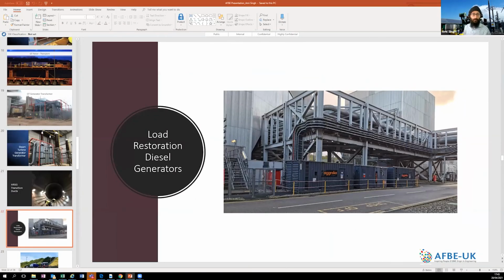At the moment we do not have a black start facility at the power station. We cannot start if the grid were to go black. We're currently out to tender with National Grid, which we'll find out by the end of this week if we've been successful or not. We need approximately 20 odd megawatts to get the station up and running, and that's just the ancillary load we have to supply ourselves in a black start environment. So we do not have that facility to do black start.